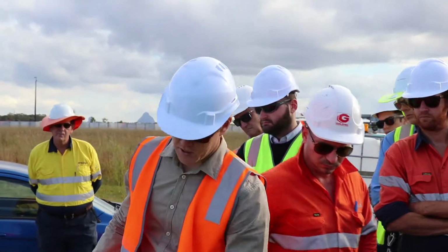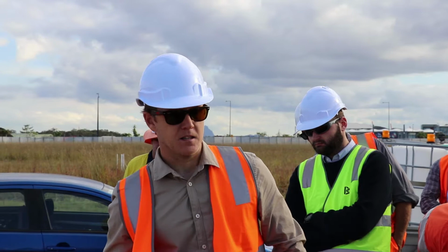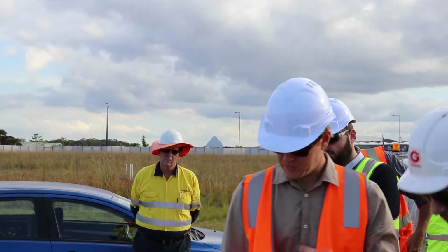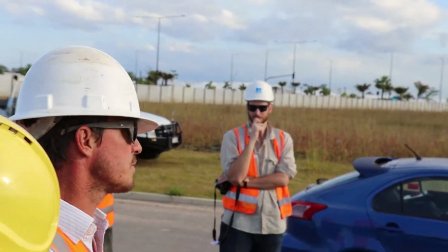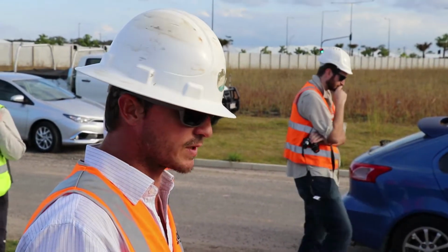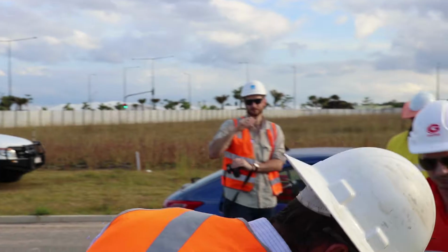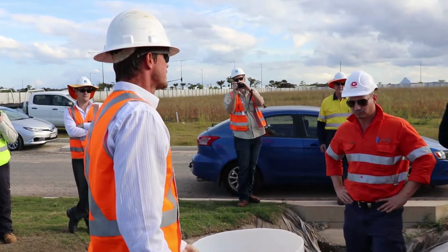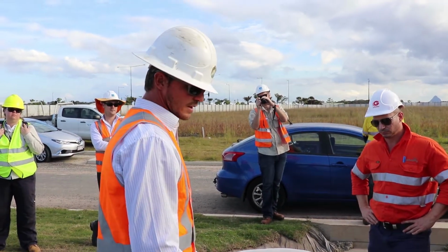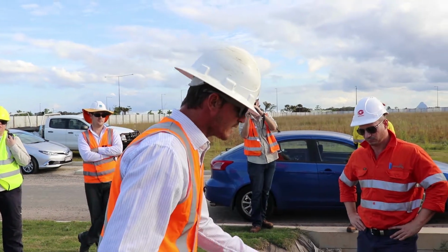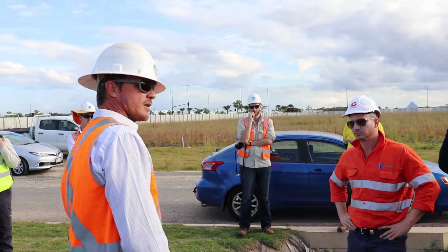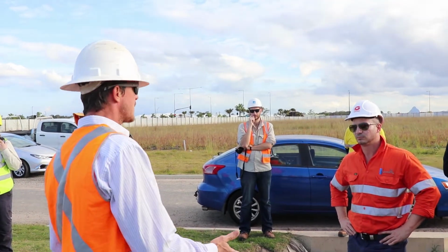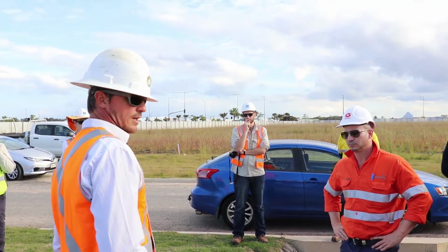Header tank, holding tank, and the bucket in the bucket. What do you fill it with? You fill the bottom tank up, you reset, so you tip out, and so there's management and maintenance with these devices. Obviously you're going to be limited to the volume of the product that you're using. So in this case, this is a 75 litre setup, but you're not going to get a full 75 litres. There's space all around, there's 20 litres there you're not going to get. So you really only got about 50 litres of potential coagulant to use.